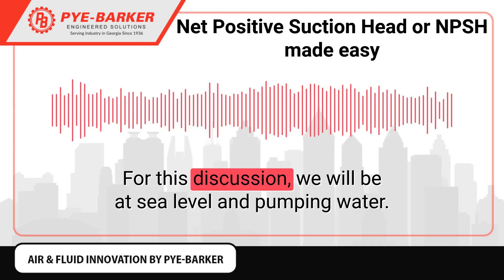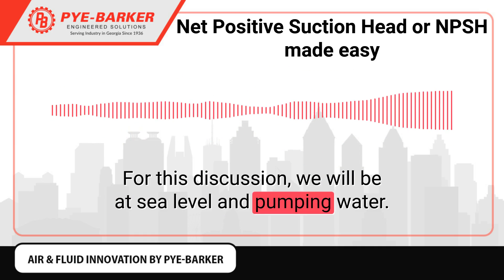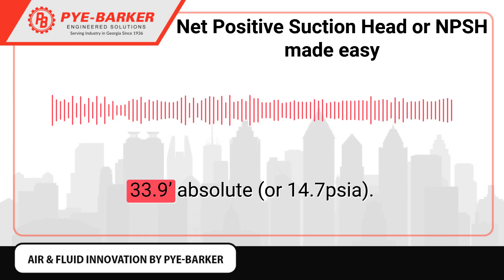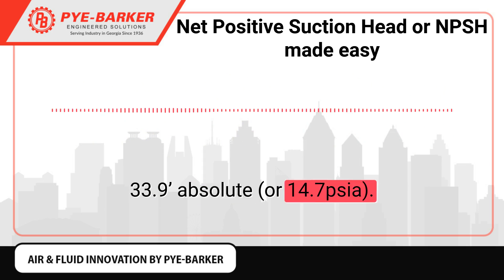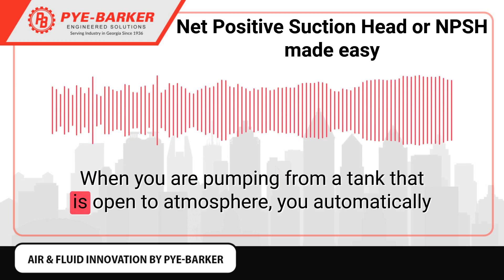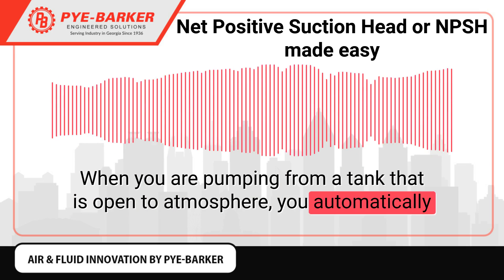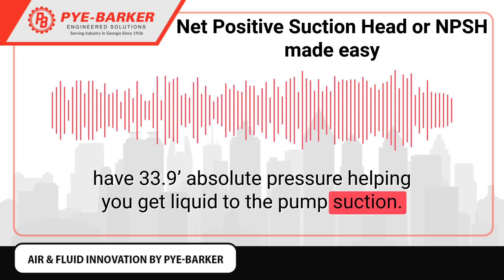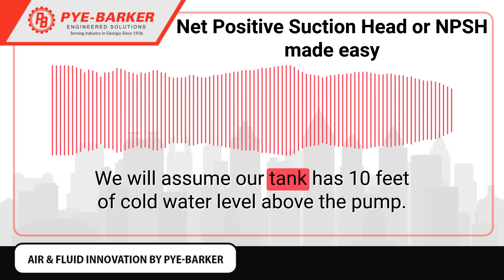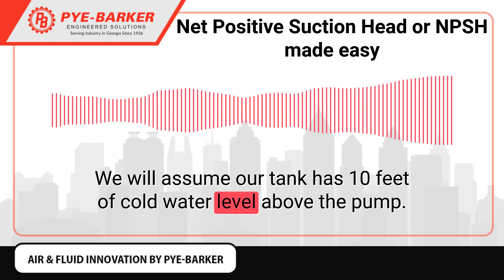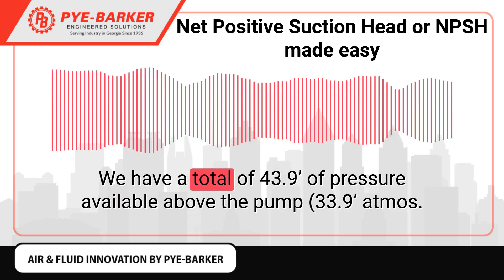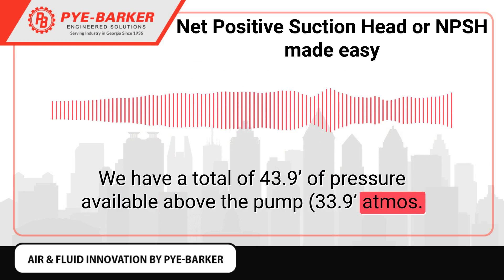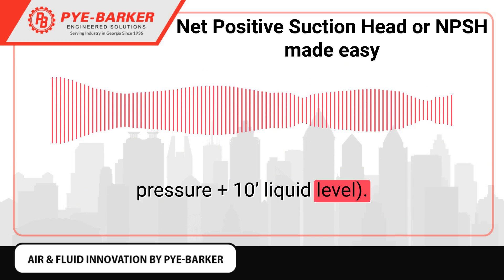For this discussion, we will be at sea level and pumping water. At 0 feet elevation, sea level, the atmospheric pressure is 33.9 feet absolute. When you are pumping from a tank that is open to atmosphere, you automatically have 33.9 feet absolute pressure helping you get liquid to the pump suction. We will assume our tank has 10 feet of cold water level above the pump, giving us a total of 43.9 feet of pressure available — 33.9 atmospheric pressure plus 10 feet of liquid level.